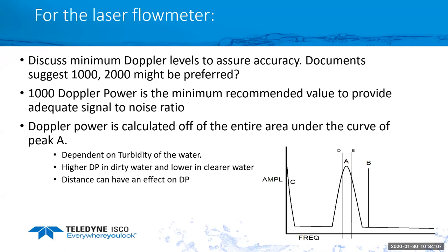The Doppler power reading that you're going to see is going to be dependent on the turbidity of the water. So the dirtier the water, the higher the Doppler signal you're going to see. The cleaner the water, the Doppler power is going to decrease. It doesn't mean that it's a better or worse reading. It just means that we have more or fewer particles in the water. And then the distance away from the water is going to have an effect on that Doppler power reading. But what we're looking for is we just want the Doppler power to be higher than the noise level. So in this example on that bottom right, C, that's just the electronic noise level. We just want to make sure that we have a higher signal than the noise, so we get accurate flow readings or velocity readings.